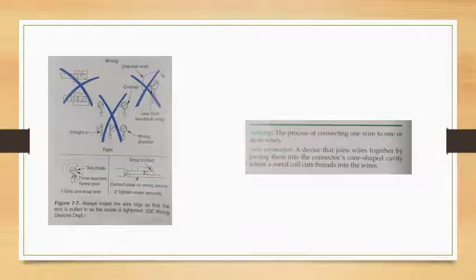Do not make a circling cut at a right angle to the insulation. It is almost impossible to control the depth of the cut in this way. A nicked conductor will break easily if it is at the point of damage. Also, a nick or groove will reduce the current carrying ability of the conductor. After you have cut away the insulation all around the wire using a whittling cut, twist the short piece of insulation. As a general rule, a little less than an inch of the conductor should be bared. This allows enough bare wire to make a proper connection. Some electrical devices have gauges for determining how much insulation to remove. See figure 7-4.